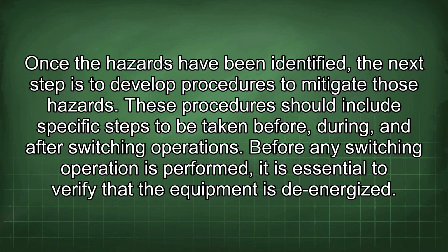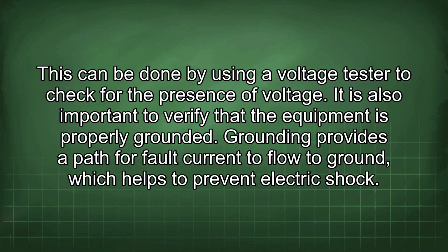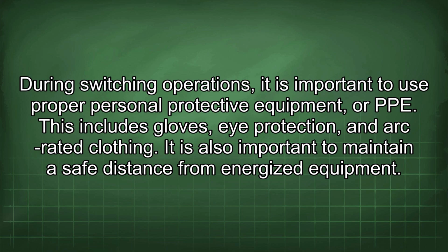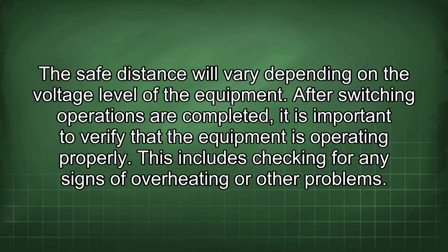Before any switching operation is performed, it is essential to verify that the equipment is de-energized. This can be done by using a voltage tester to check for the presence of voltage. It is also important to verify that the equipment is properly grounded. Grounding provides a path for fault current to flow to ground, which helps to prevent electric shock. During switching operations, it is important to use proper personal protective equipment, or PPE. This includes gloves, eye protection, and arc-rated clothing. It is also important to maintain a safe distance from energized equipment. The safe distance will vary depending on the voltage level of the equipment.